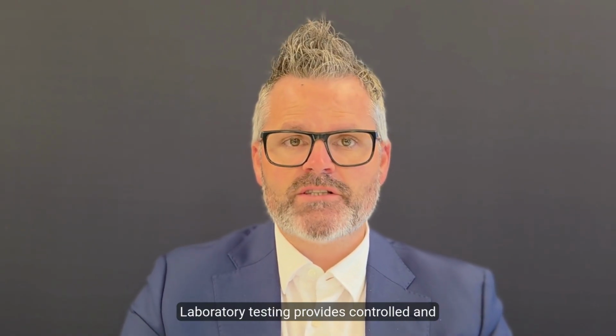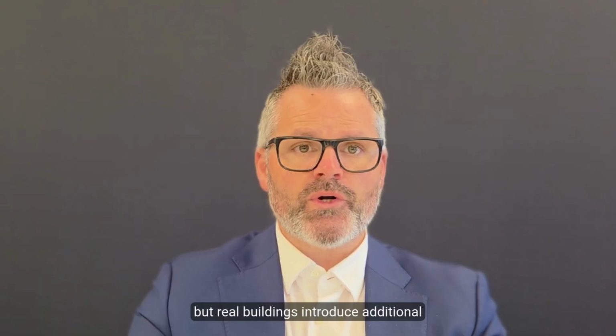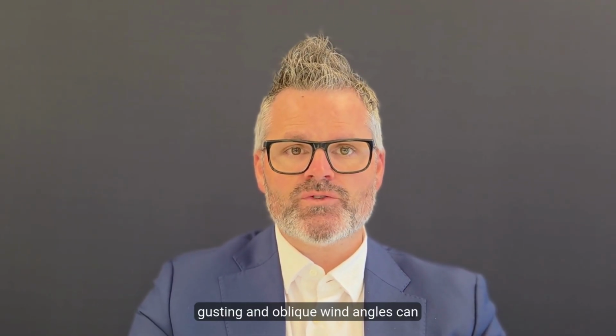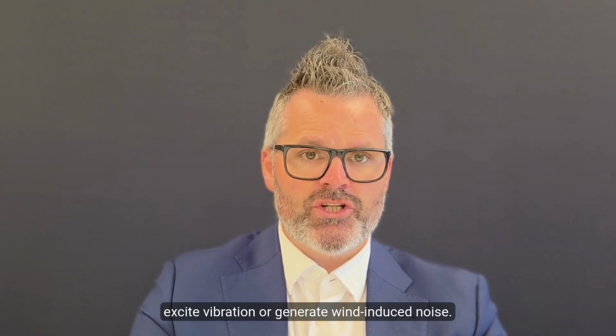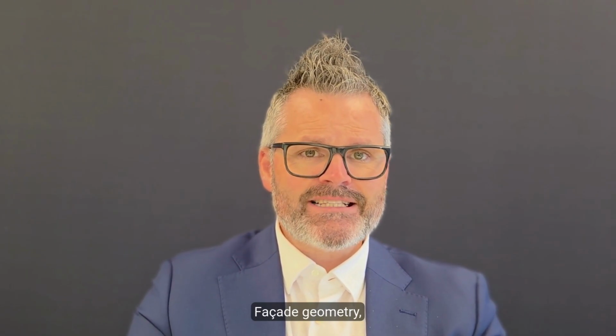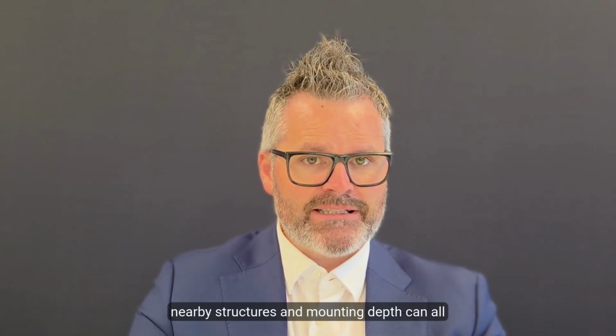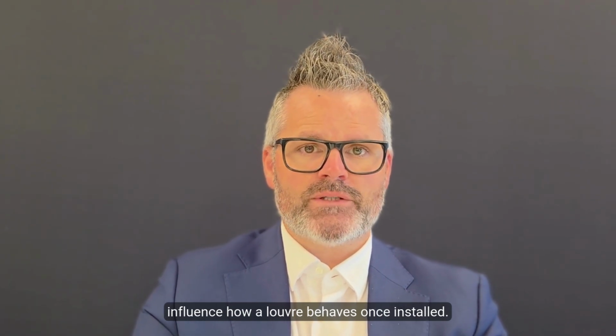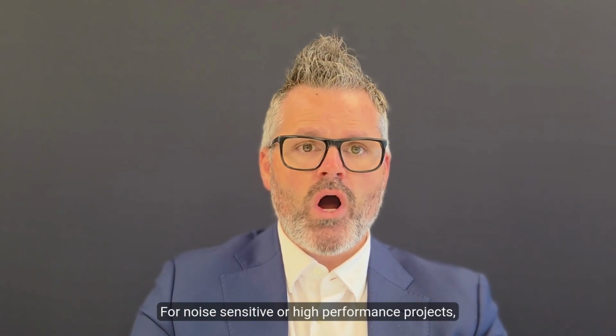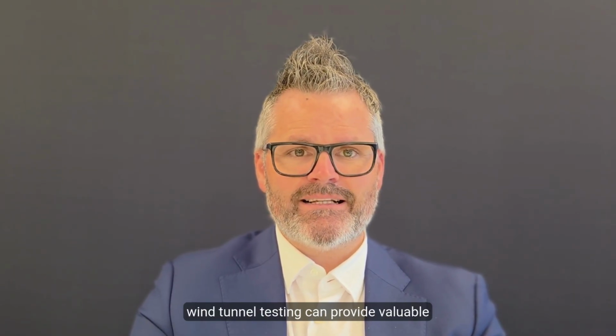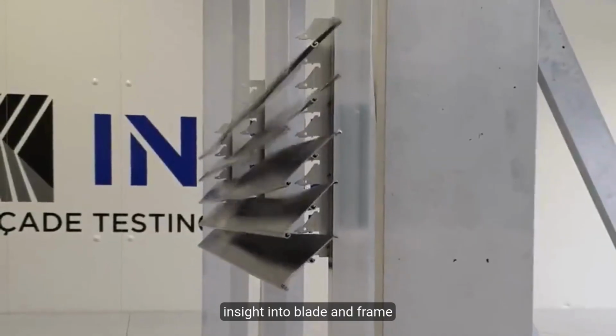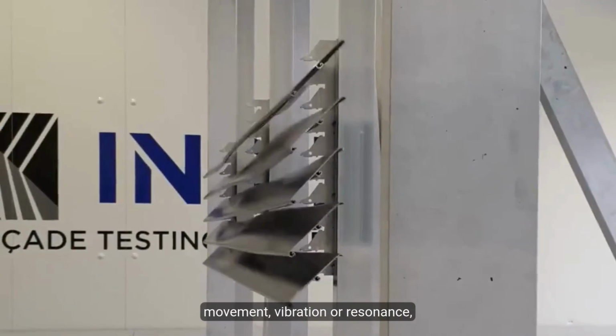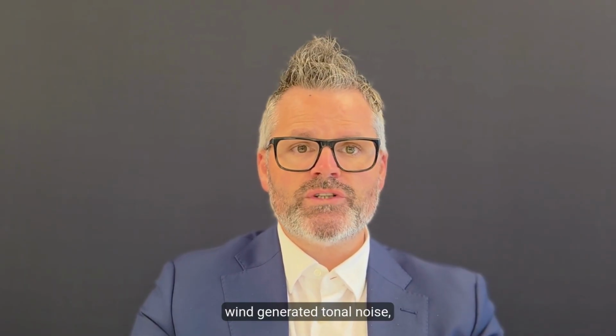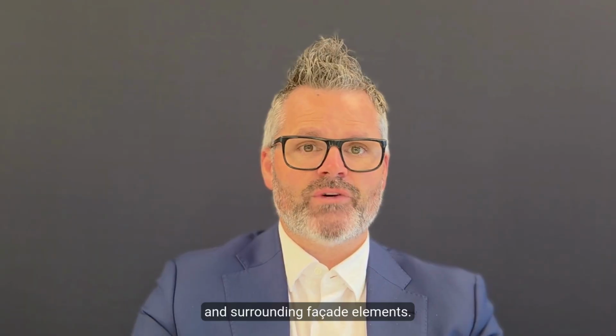Laboratory testing provides controlled and repeatable results, but real buildings introduce additional variables. Wind rarely approaches a facade uniformly. Turbulence, gusting, and oblique wind angles can excite vibration or generate wind-induced noise. Facade geometry, nearby structures, and mounting depth can all influence how a louver behaves once installed. For noise-sensitive or high-performance projects, wind tunnel testing can provide valuable insight into blade and frame movement, vibration or resonance, wind-generated tonal noise, and interactions between the louver and surrounding facade elements.